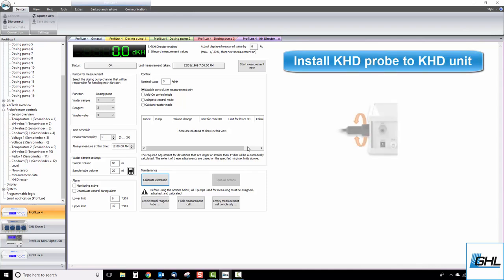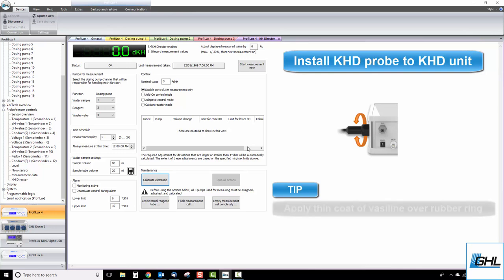When installing the probe, make sure the rubber ring is correctly positioned and the locking nut is tight enough so that it creates a watertight seal. If you need to create a tighter seal, you can do so by rubbing a thin coat of Vaseline over the rubber ring.